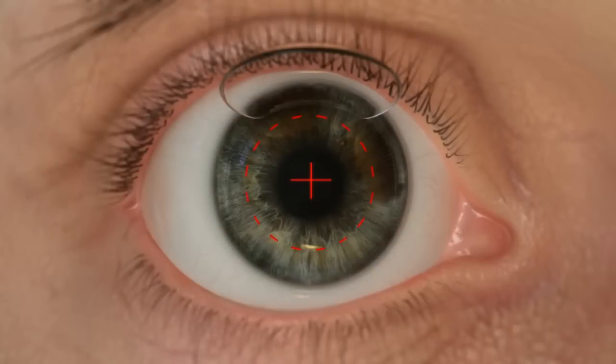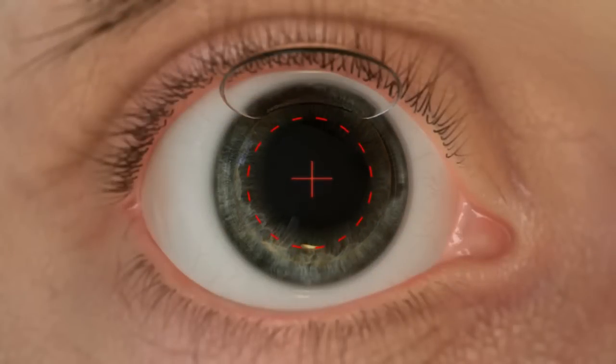Pupil dilation causes pupil centroid shift, or a shift in the visual axis. The Wavelight EX500 Excimer Laser is able to compensate centroid shift and make necessary adjustments to align with the predetermined treatment profile.